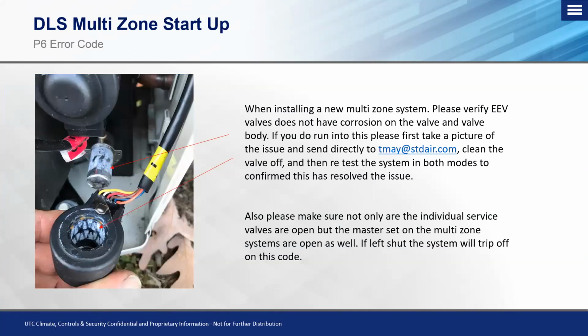The last quick thing I wanted to cover is if you have a P6 error code on a newer multi-zone system. One thing that we have found, if you look on the picture, is this excess oxidation or corrosion that's building up inside of the body of the expansion valve and also on the post.